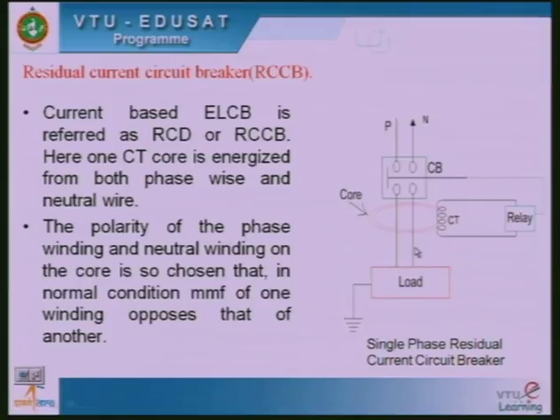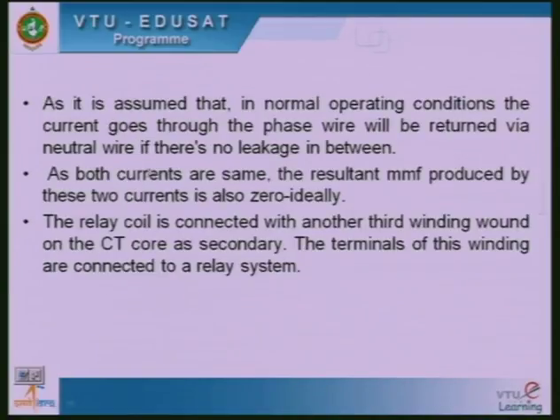In case of any fault, the current will flow in a different way. It is assumed that in normal operating condition the current goes through the phase wire and returns via the neutral wire, there is no leakage in between, okay. As both currents are the same, the resultant MMF produced will be the same. So therefore net MMF will be 0, because each wire is producing the same amount of EMF and acting in different directions. The relay coil is connected with another third winding wound on the CT core as secondary, okay.